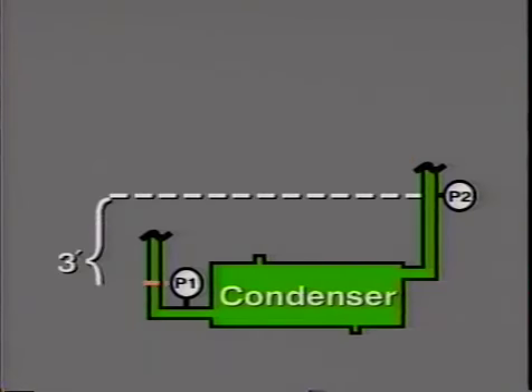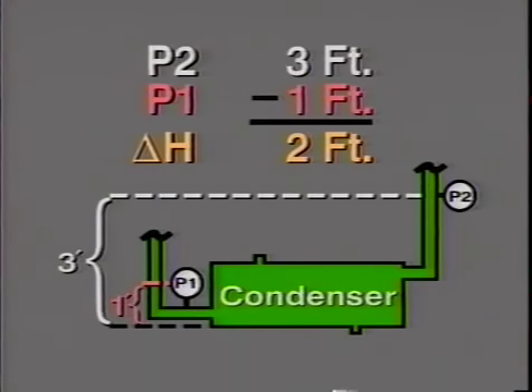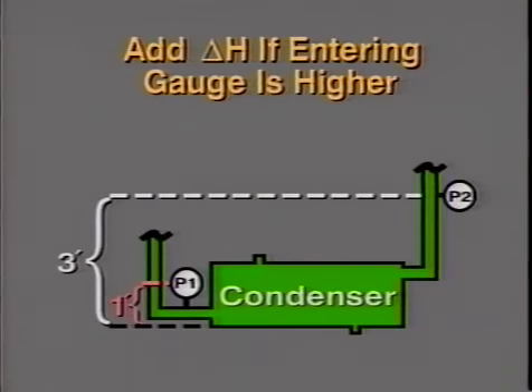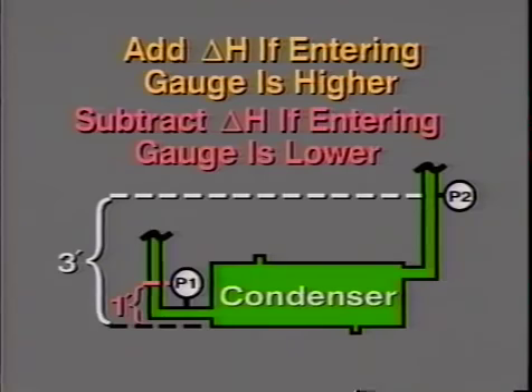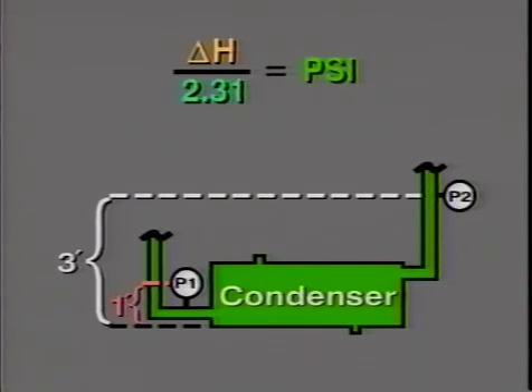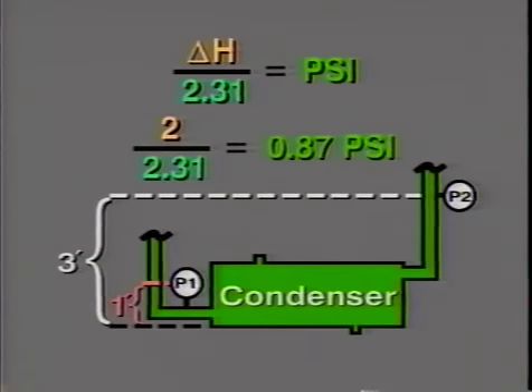Next, determine the difference in height, delta H, between the gauges, where delta H equals 3 feet minus 1 foot, which equals 2 feet. A rule of thumb is to add delta H if the entering gauge is higher, or subtract delta H if the entering gauge is lower. Next, we need to convert feet to psi using the following equation, where delta H divided by 2.31 equals psi, or 2 divided by 2.31 equals 0.87 psi. 2.31 is the conversion factor to change feet of water to psi, where 2.31 feet of water equals 1 psi.